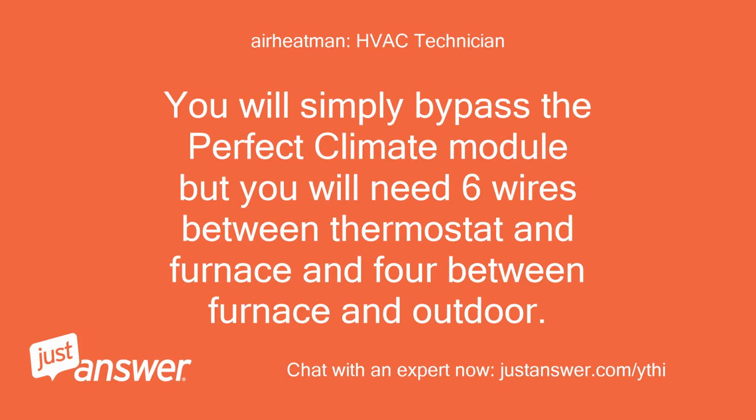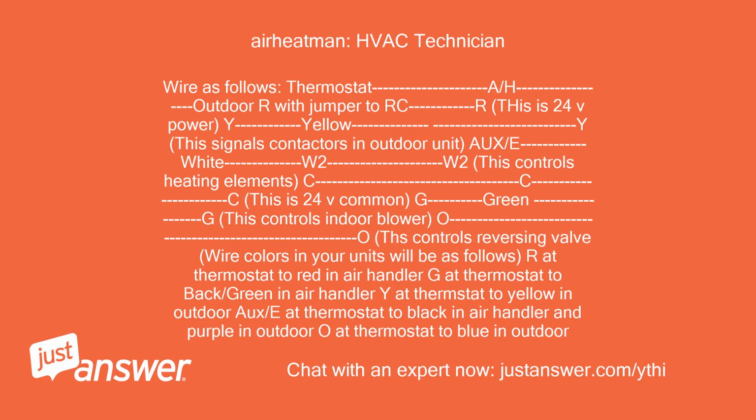You will simply bypass the perfect climate module, but you will need 6 wires between thermostat and furnace and 4 between furnace and outdoor. Wire as follows: thermostat, AH, outdoor. R with jumper to RC, R, this is 24V power. Y, yellow, Y, this signals contactors in outdoor unit. AUX/E, white, W2, W2, this controls heating elements. C, C, C, this is 24V common. G, green, G, this controls indoor blower. O, O, this controls reversing valve.